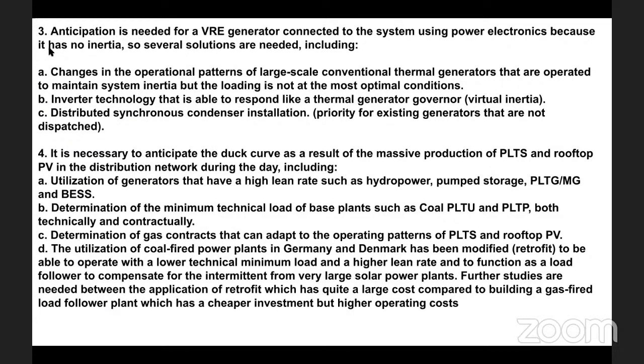it has no inertia, so several solutions are needed, including: A, changes in operational patterns of large-scale conventional thermal generators that are operated to maintain system inertia, but the loading is not at the most optimal conditions. B, inverter technology that is able to respond like a thermal generator governor, virtual inertia. C, distributed synchronous condenser installation, a priority for existing generators that are not dispatched.